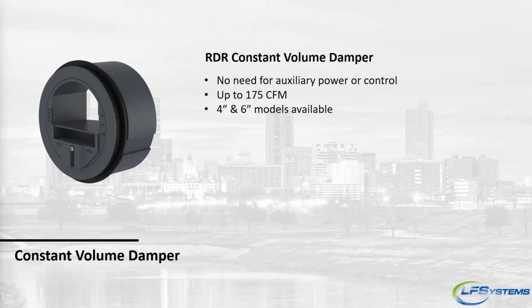Now, that does require a constant flow, constant volume system. So at that point, if we're going with the RDR, we are not going to have a modulating system, though we can, with our fan and our controls, still meet all the other code requirements and adjust that speed much quicker than if you were to do it with a standard balancing system.